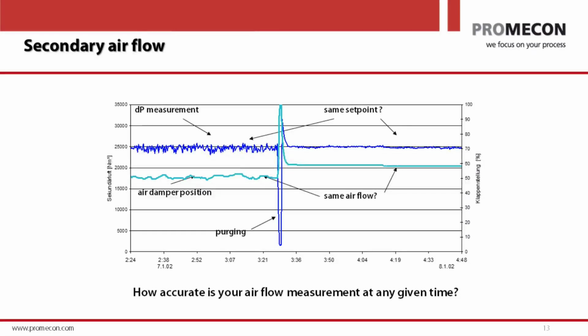The set point is 25,000 norm cubic meters, and the DCS system will always control the damper to reach that set point. So the operator is looking at 16 burners. He sees 16 times 25,000 norm cubic meters, and he basically thinks that he is fine, but he is not. And the deviation that you see is not 1 or 2%. This is massive. This is really a big change.